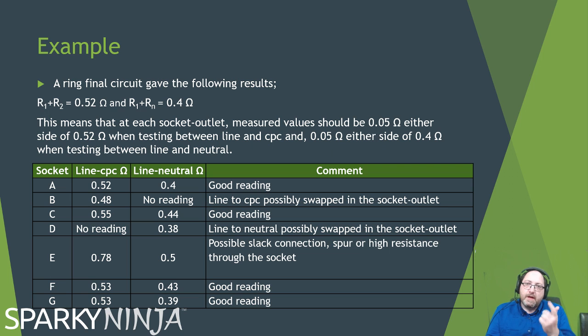E, got a slight increase in resistance here. This doesn't mean a loose connection or a disconnected socket, because if I had a loose connection, then my first test, my end-to-ends, wouldn't have been there. It's likely to be either a twisted pair that has become slack, or a high resistance through the plug, if I've measured through the plug, or it could even be that this socket's a spur, so there's an increased resistance in that cable supplying this socket outlet. F and G are just good readings, so they're fine.